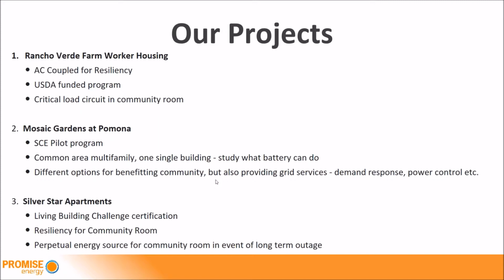From just a mechanical interconnection capacity standpoint in a standard campus-style affordable housing facility, most of the time the utility interconnection points are located outdoors, so it's difficult to find energy storage devices rated for outdoor installation. It's not that they don't exist, but they're few and far between, and that was a challenge.